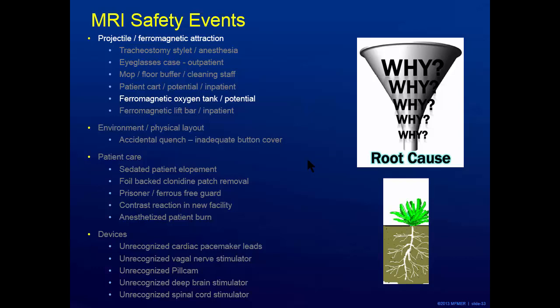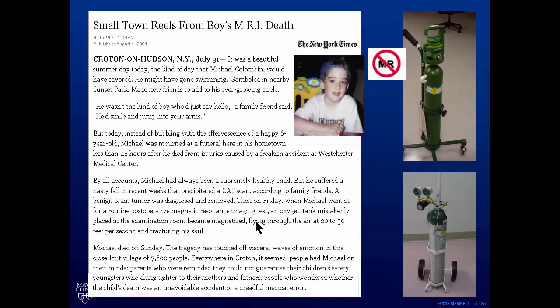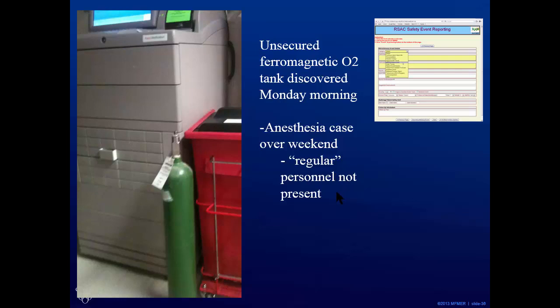We had a potential incident several years ago. We came in one Monday morning to find a ferromagnetic oxygen tank standing by itself about 12 to 15 feet away from the Zone 4 door. This got our attention big time. We realized there had been an anesthesia case over the weekend, and this is a reminder of the tragic death of Michael Colombini, also as a result of a ferromagnetic oxygen tank. We discovered this tank and realized it was one of these one-offs — there had been an anesthesia case late Sunday night when the regular personnel were not there, and the tank was just left.